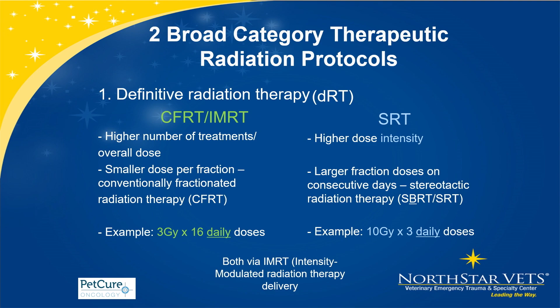Both of these treatments are intensity modulated delivered. What that means is there's a multi-leaf collimator on the machine. So rather than just opening up an aperture and that hole is where we shine the radiation through and everything gets the same dose, there are individual lead leaves that help to shape the field. So that knocks off the corners of unnecessary radiation. I haven't seen a square or a rectangular tumor out there, so we can shape it to the contours of the tumor itself. But those leaves actually trickle the radiation dose over the tumor volume. So we can pinpoint and choose which parts of the tumor get a higher dose. So maybe that's the center of the tumor because we just want to blast it to the end of the day. And the other parts of the tumor that are close to maybe the frontal part of the brain, if we're talking about a nasal tumor, or right next to an eyeball, we want to give a prescription dose, but we want a steep dose fall off at that edge so we're not getting unnecessary dose to the eye. That's what the multi-leaf collimator does, it makes this fan-shaped beam and it's trickling the dose across the 3D tumor volume.